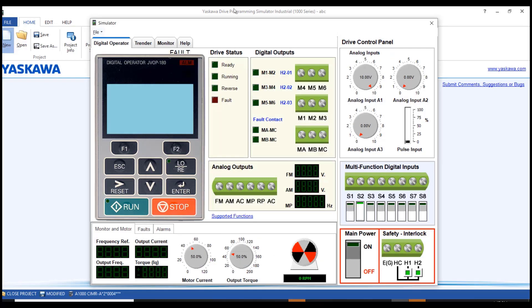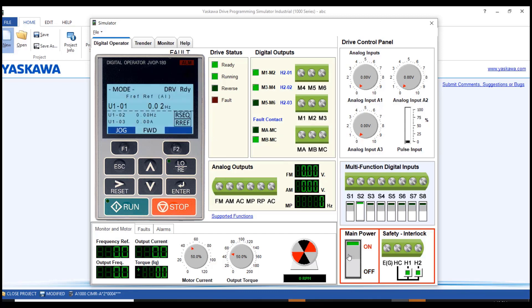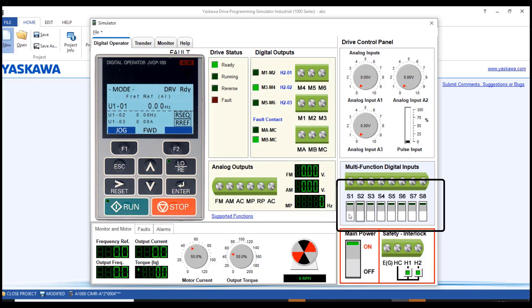This is your interface for the simulator. The drive is currently in off condition — no display. First, power on the drive by clicking the power button. Now the drive is on. By default, the drive takes its frequency reference from the analog input — a zero to ten volt signal. At zero volts input, frequency will be zero. At the maximum value of ten, frequency will be 60 Hz, which is the default maximum frequency.